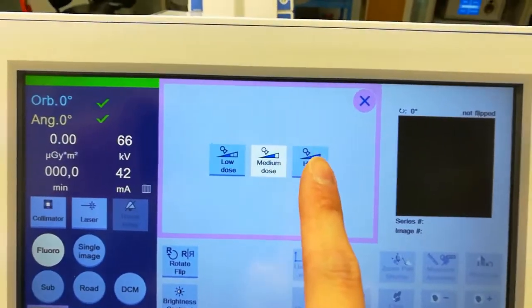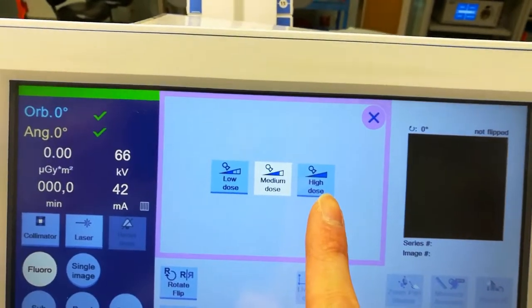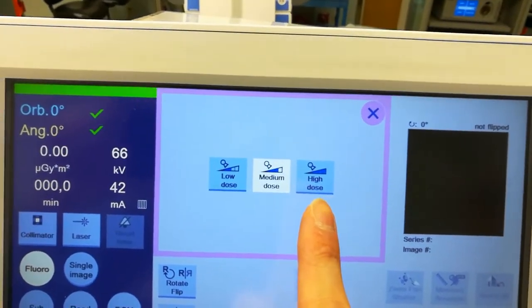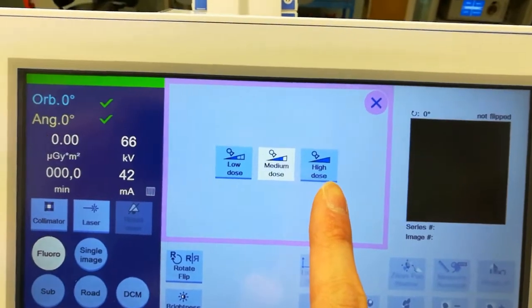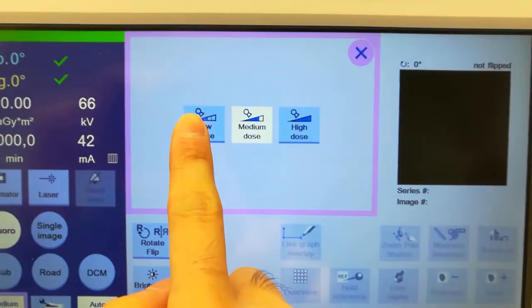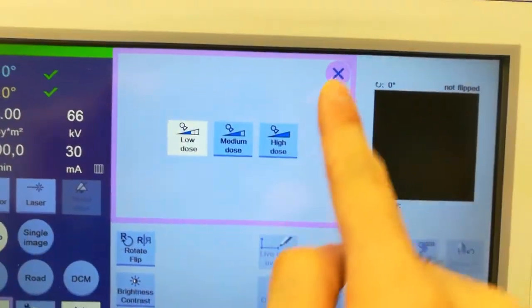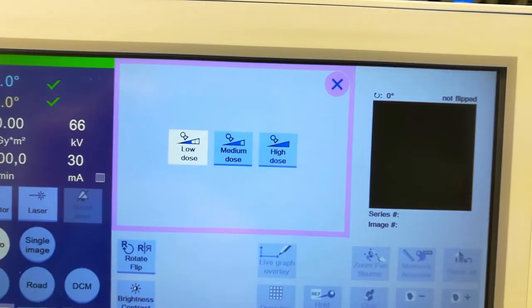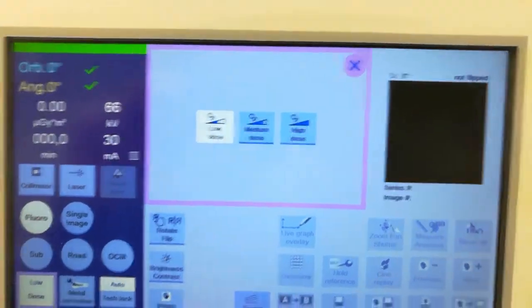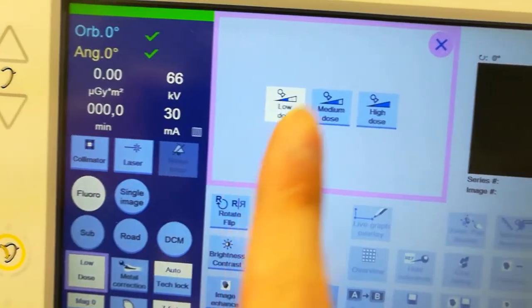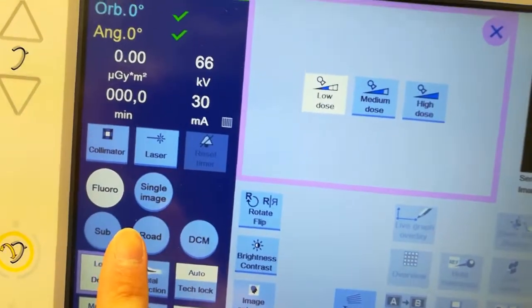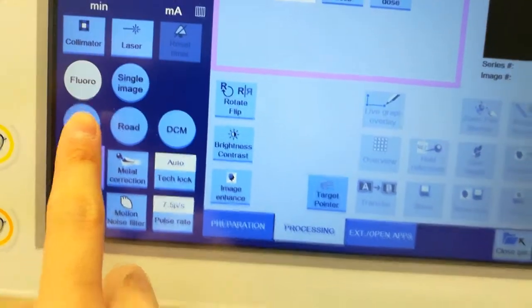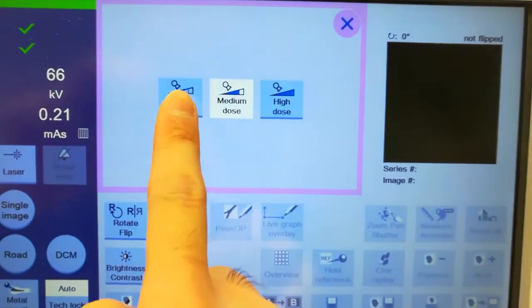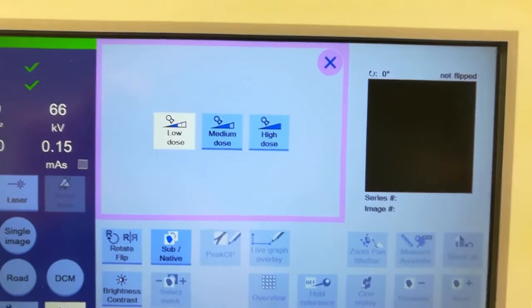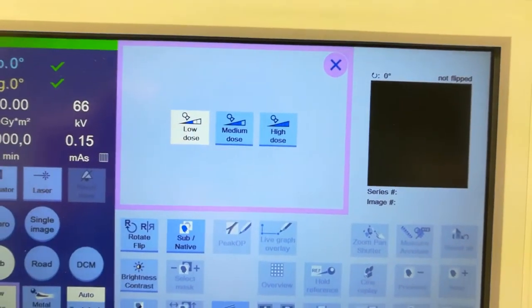Click it, and you can even put it on high dose, which is equal to high level fluoro on your OECs, otherwise known as eyeball plus. So I just set it to low dose for most of the cases we do here. However, notice, even though I set the fluoro mode to low dose, that does not automatically set the subtraction to low dose. Subtraction defaults back to medium dose. So just make sure you change both if that's the route you're planning to go.